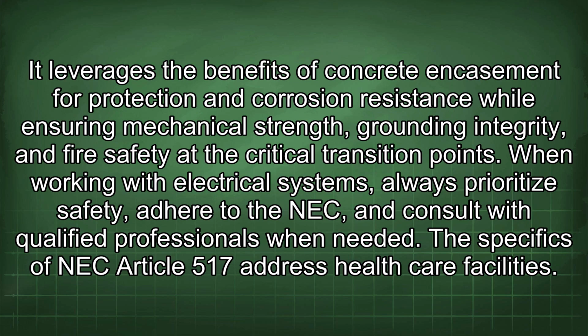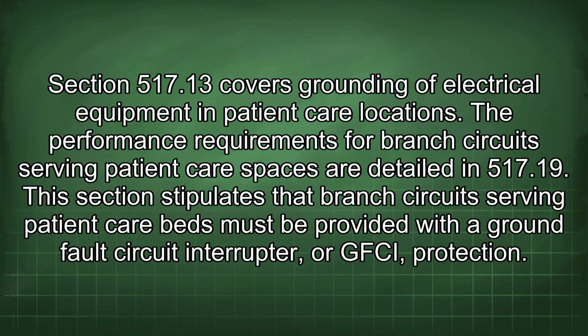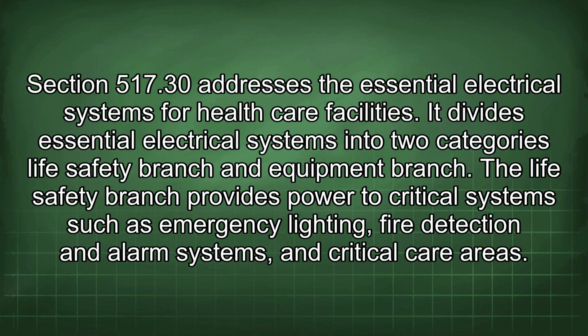The specifics of NEC Article 517 address healthcare facilities. Section 517.13 covers grounding of electrical equipment in patient care locations. The performance requirements for branch circuits serving patient care spaces are detailed in 517.19. This section stipulates that branch circuits serving patient care beds must be provided with a ground fault circuit interrupter, or GFCI, protection. Section 517.30 addresses the essential electrical systems for healthcare facilities.